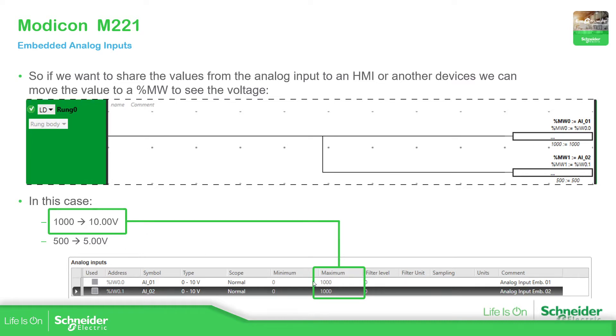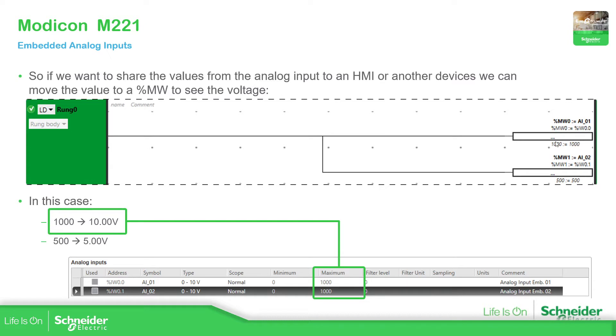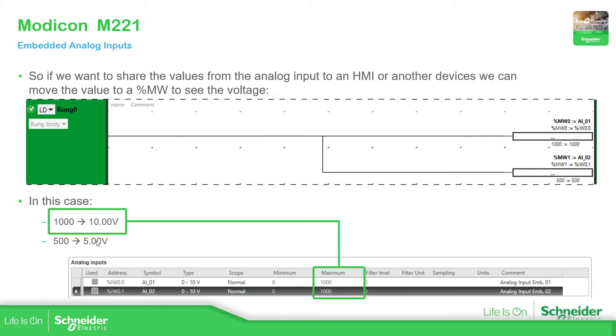As you can see here, by default we are not able to change it. The minimum is zero and the maximum is 1000. So this 1000 is 10 volts. In the analog input one, I have assigned 10 volts and this is the raw value - 1000 which means 10 volts. And if I assign to the second input 500, it means that I have 5 volts in the input.